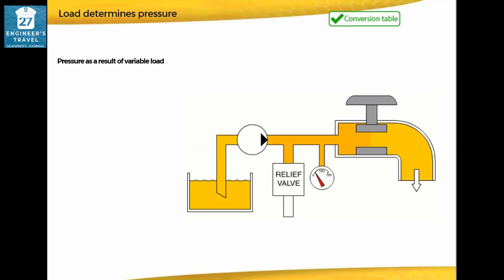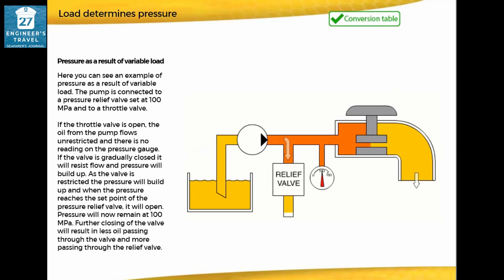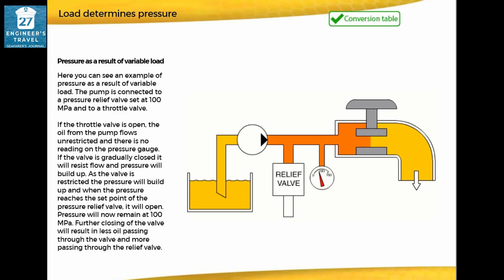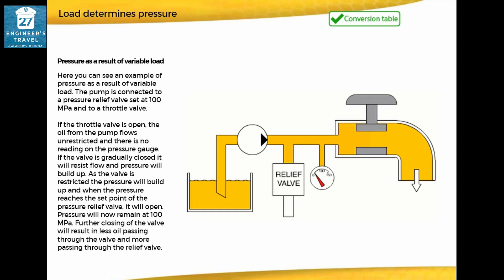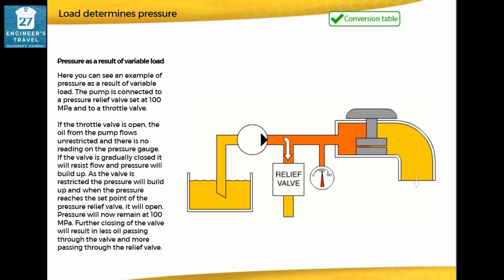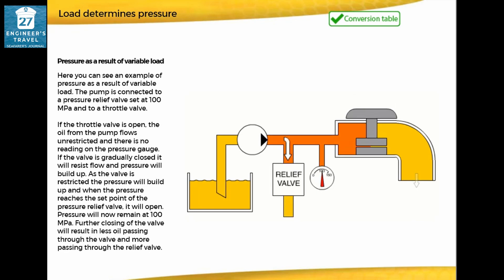Pressure as a result of variable load: the pump is connected to a pressure relief valve set at 100 megapascals, and to a throttle valve. If the throttle valve is open, the oil from the pump flows unrestricted and there is no reading on the pressure gauge. If the valve is gradually closed, it will resist flow and pressure will build up. When the pressure reaches the set point of the pressure relief valve, it will open, and pressure will remain at 100 megapascals. Further closing of the valve will result in less oil passing through the valve and more passing through the relief valve.